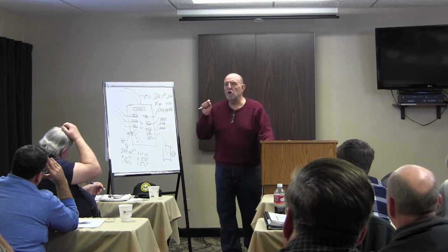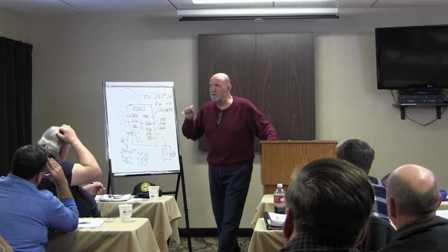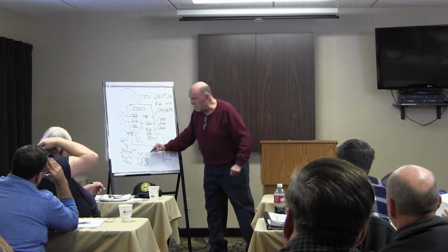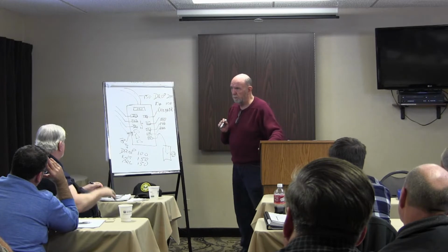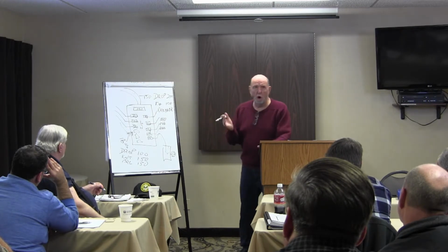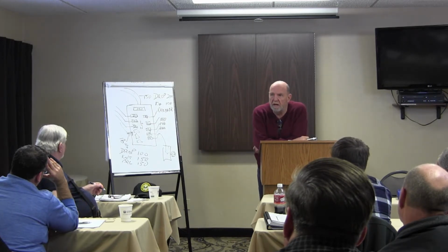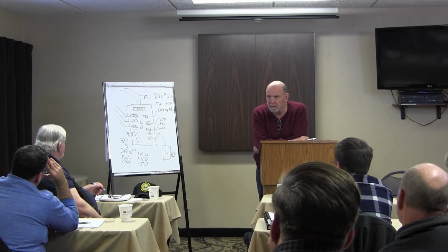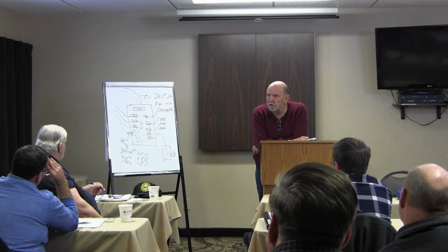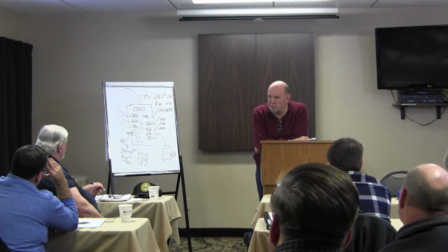Remember, whatever your service size is determined to be out of these three, that then determines what the fault is. Which always means we're going to wind up changing the breaker size to match the smallest size. So don't write your defect up, and I've seen it done that way, as wire's too small.